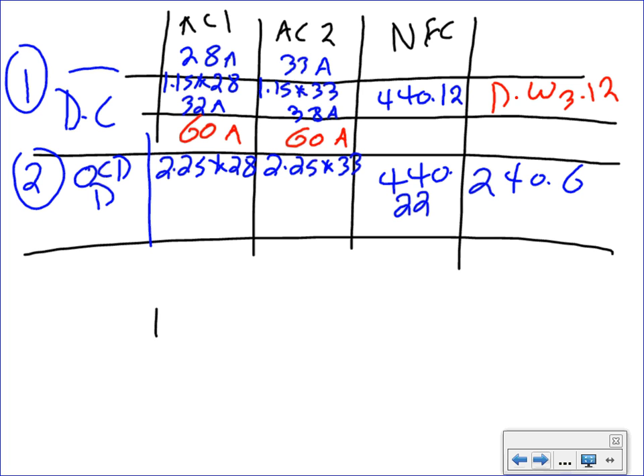You have a problem, Holly? No, I'm just considering it the other way. If it doesn't start, it allows you to go to the max; we're assuming it's not going to start. What's the calculation, Brooks? The first one is 63 amps. The second one is 74 amps. These are obviously not standard, so your three options are going to the bar, crying, and custom design 63 amps, or go down, because it doesn't ask you to go up. So what's the next standard size down from 63? 60 amp. How do you know where they are? From 240.6. Okay, how about 74? Do we have a 70 amp? Okay, 70 amp.